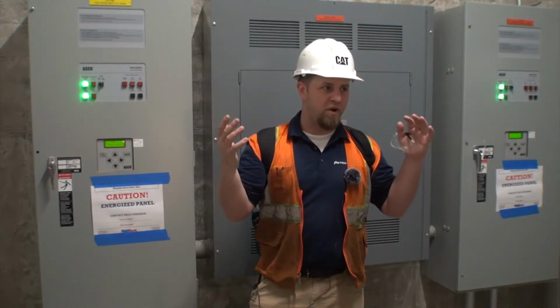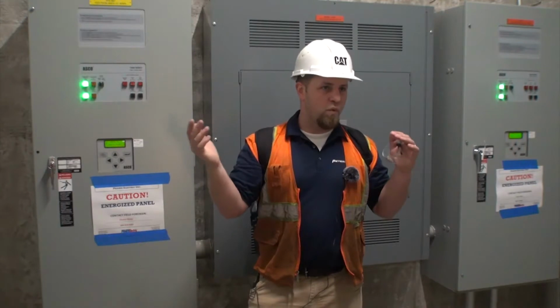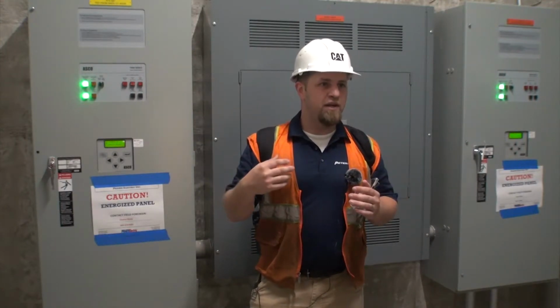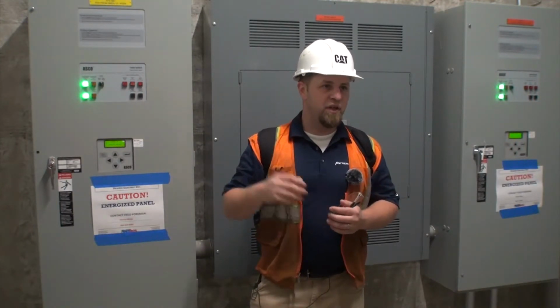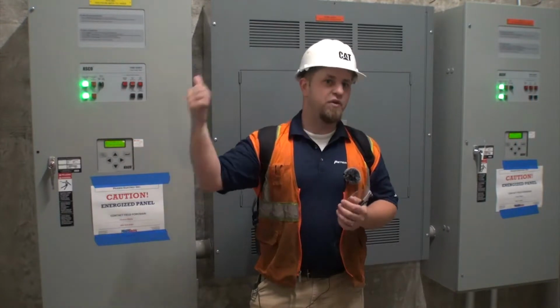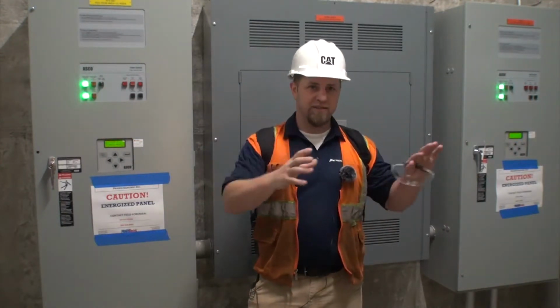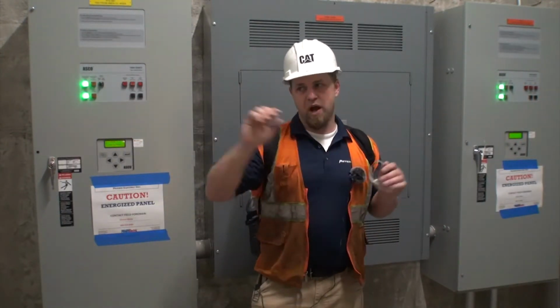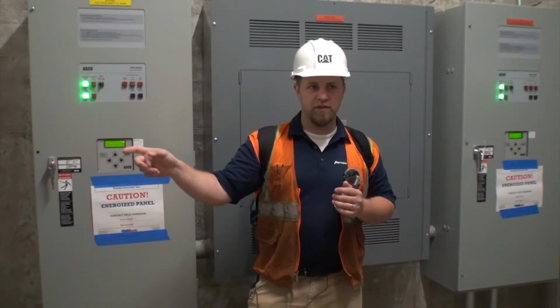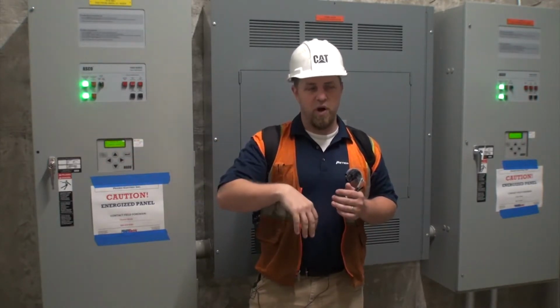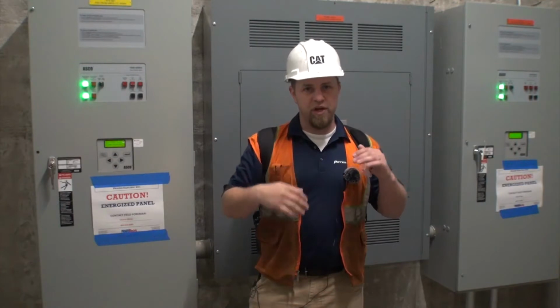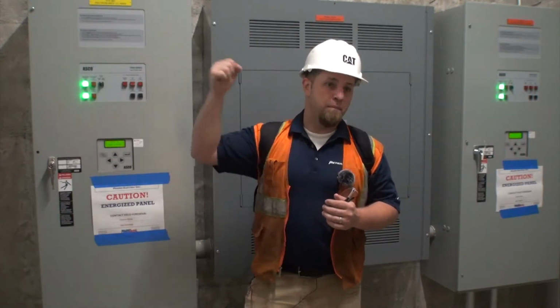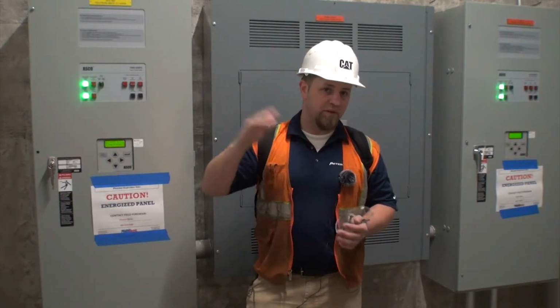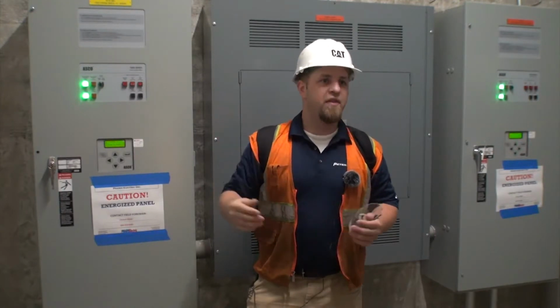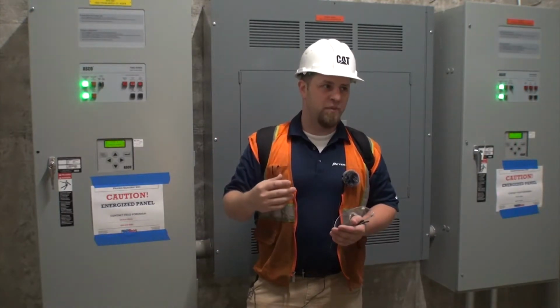So if the power goes out and it doesn't transfer one way or another, when I get here the first thing I'm going to ask is where is your breaker there? I know there's the breaker on the generator, so I can safely shut that one off, but I'm going to want to know where this one is, and also where your load breaker is. I'm going to shut off all three, open the door, manually transfer it to whatever source I want it to be on, then slowly reverse the process.